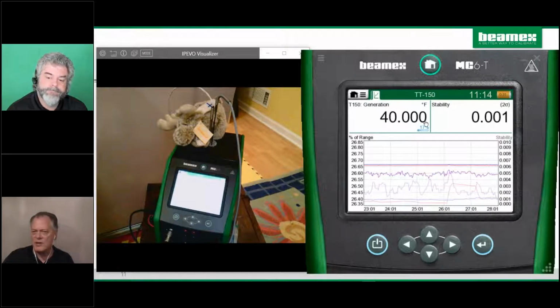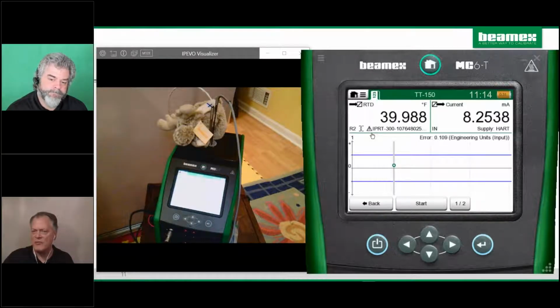So my internal temperature reference is trying to control to exactly 40. But remember, I said my traceability is coming from this reference probe. It's called the IPRT 300. So it's sitting here close to 40, but it's actually saying true temperature is a little bit lower. But here's the milliamps for the 0 to 150 range, and it's plotting right here. So it's within 1/10 of a degree. So it's really pretty good.